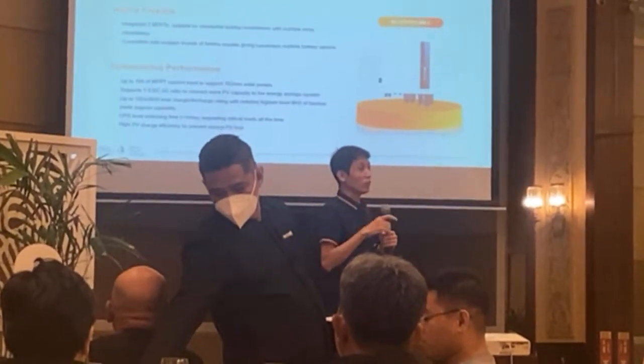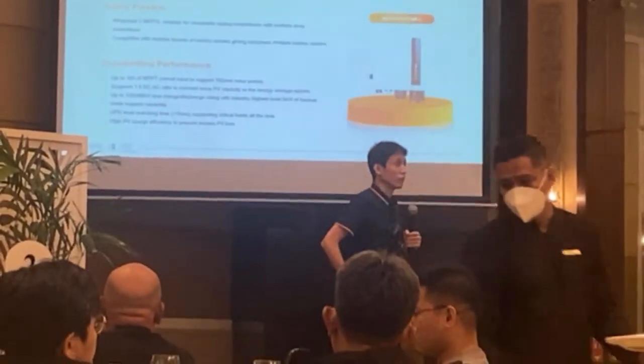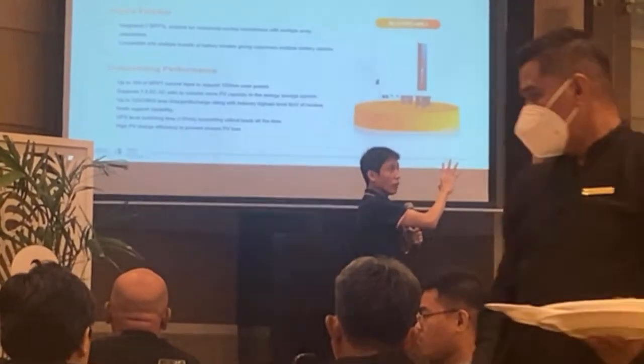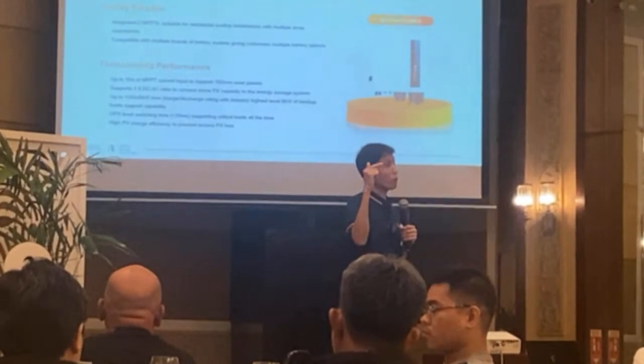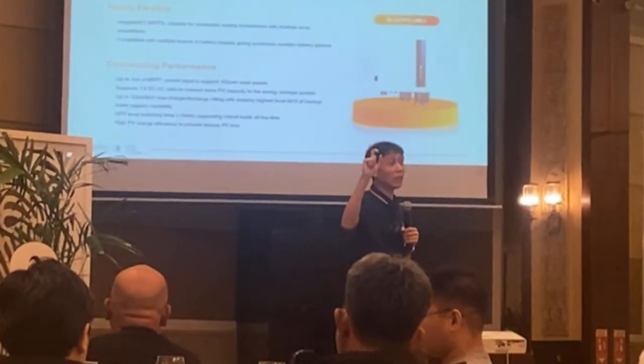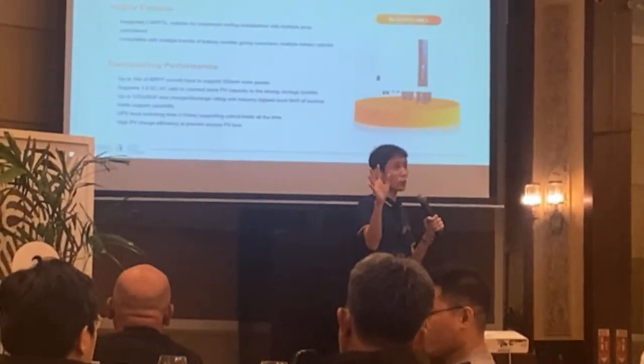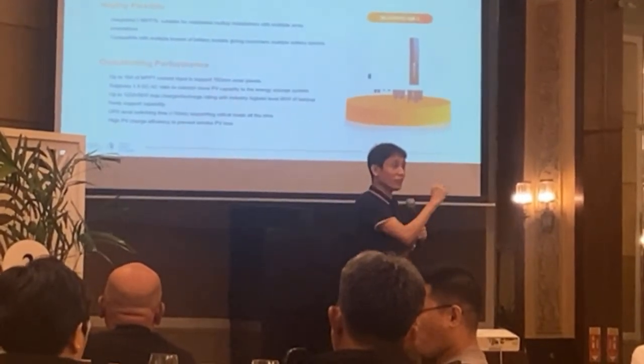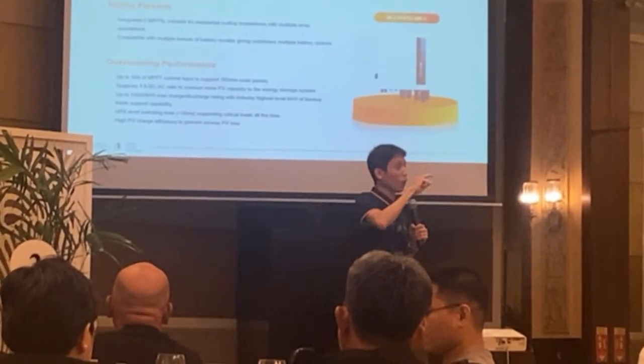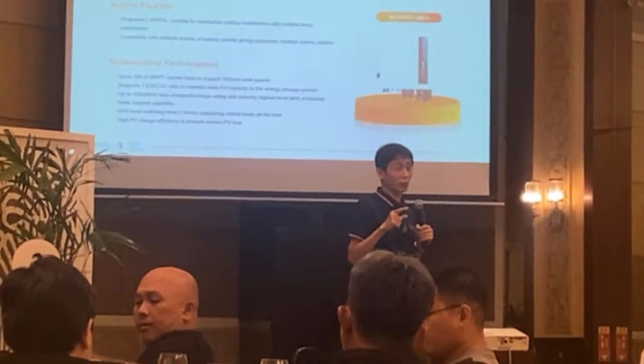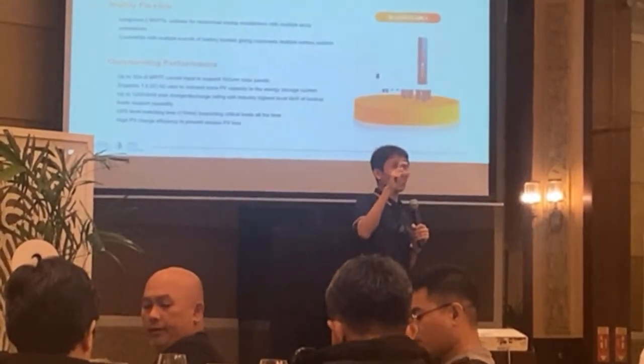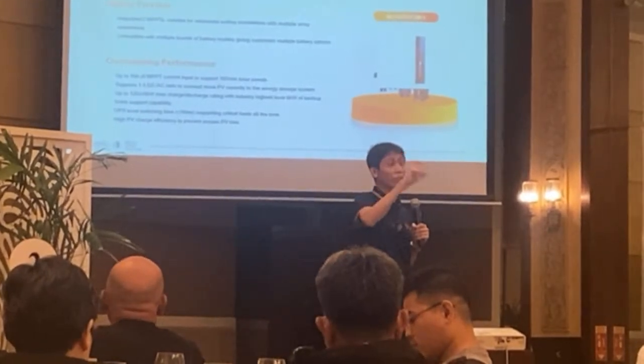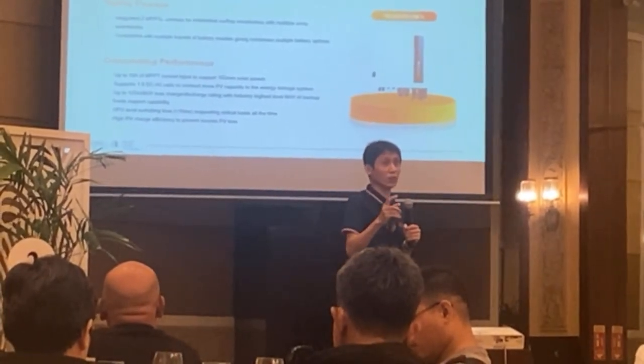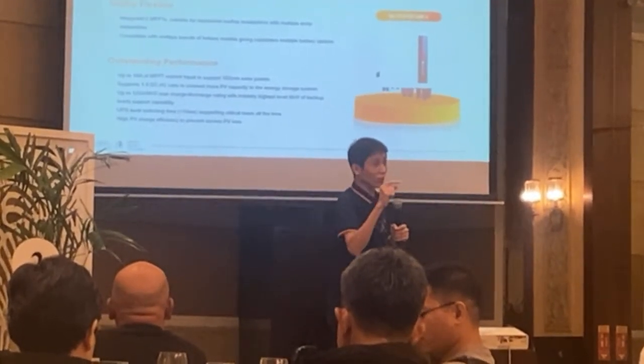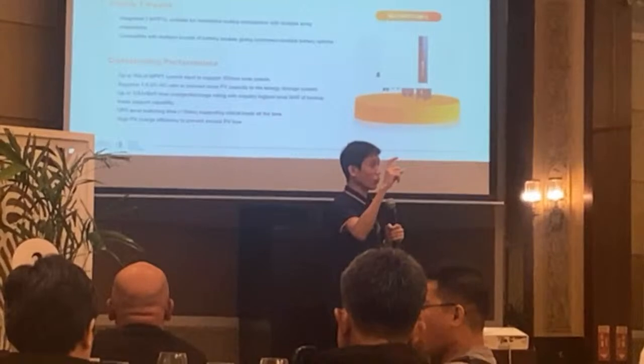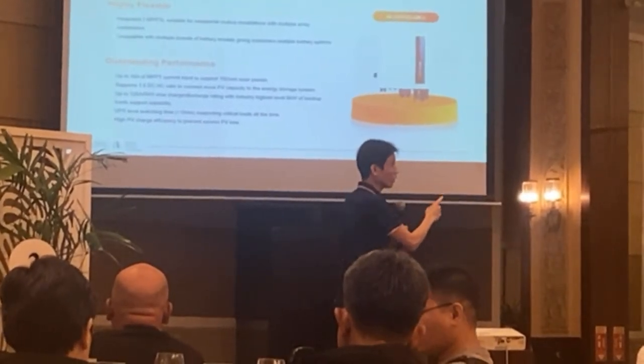If it's 0.33 amps right now, right? Yeah, in the inverter there's a way to change the CT ratio. Yeah, on the CT meter, on the ratio, because that's being fed from your meter. It's not being fed from the CT itself. So there are two different communications involved. If it's CT, now your inverter acts as the one who will interpret based on the ratio that's being given by the meter itself. So regardless whether it's 5 amps secondary or 1 amp secondary, as long as the ratio is correct, all you have to do is calculate it and put it in the inverter, that's fine.